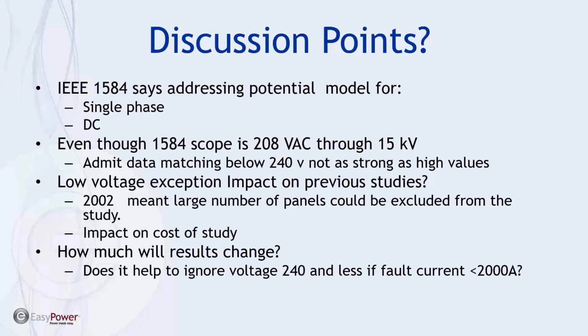For instance, does it help to ignore voltage of 240 volts or less if the fault current is less than 2000 amps, which was the cutoff point for the discussion about including low voltage analysis? Again, these are discussion points that I would suggest impact the cost of the study that I'm about to do, and it should also be somewhat gauged by the client's need to either maintain compliance or achieve compliance, whether or not the method that's prescribed in 1584 and NFPA 70E fits the needs of his particular business or operation.